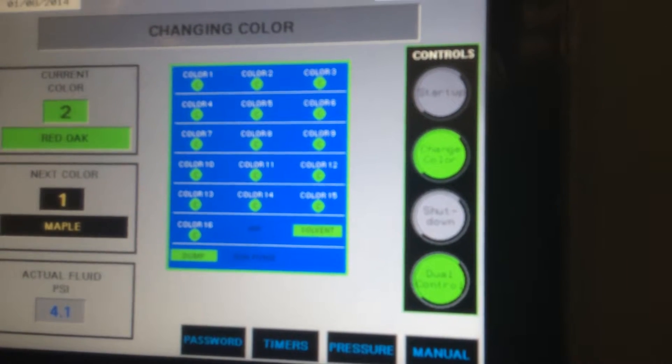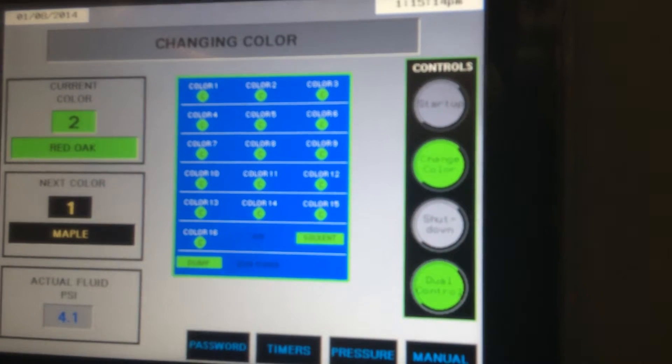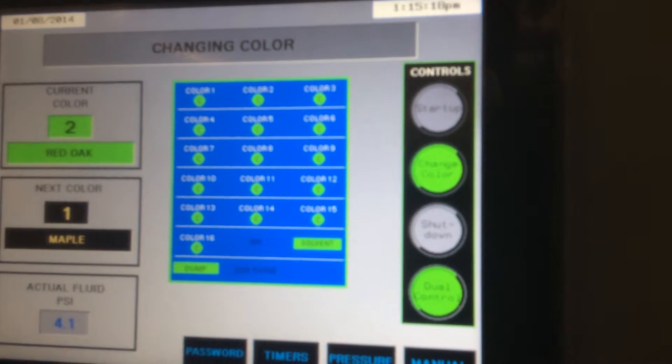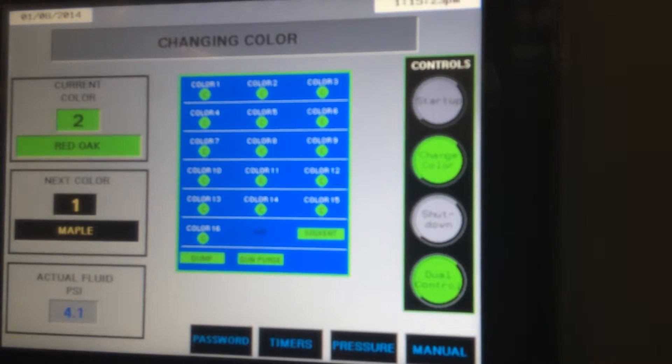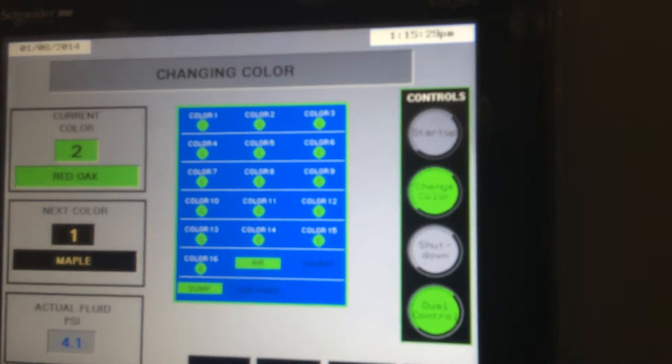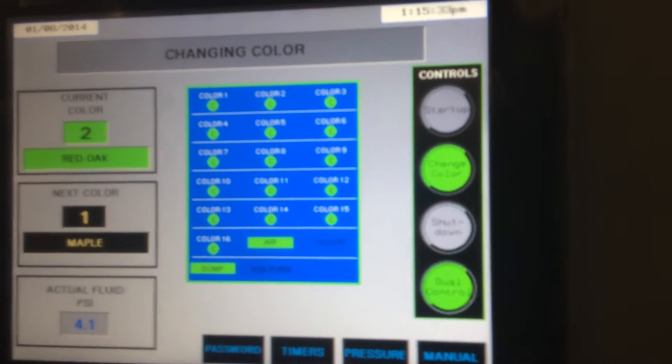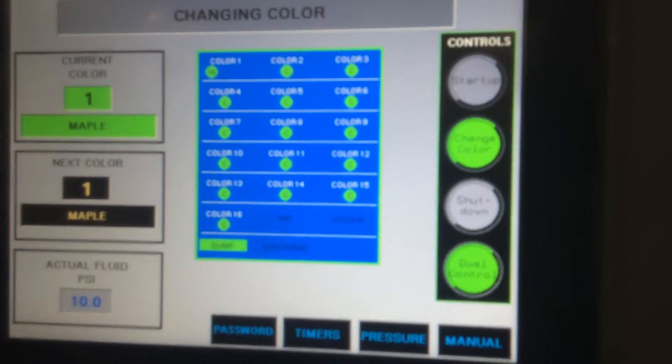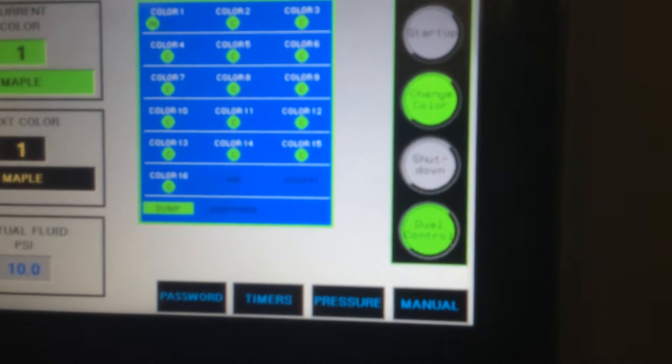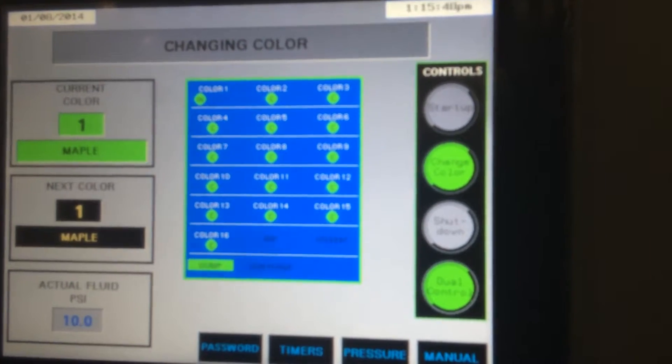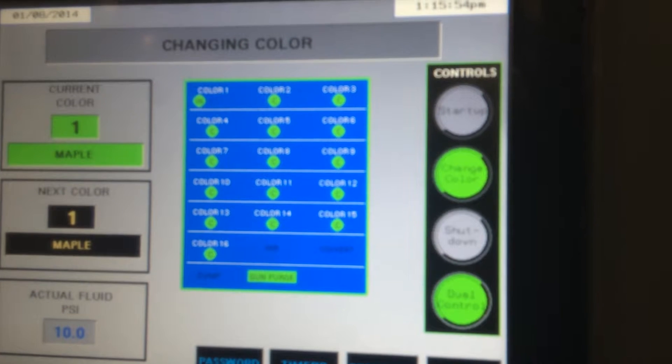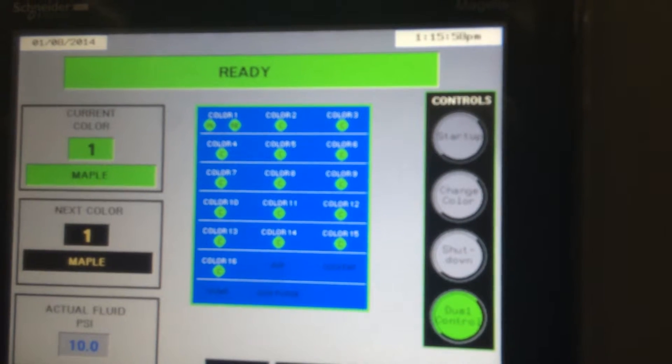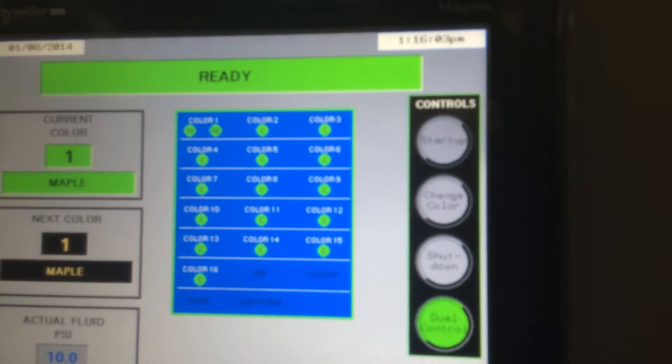You can hear the air solvent in the background. It's now triggering through the guns. It's now pushing all of the solvent out with air. The reason we put the purge to solvent is we don't want to contaminate the virgin stain. So you have good color consistency. We're now loading color one into the system, pushing air out through the dump. Gun's now trigger to load. It's now back into circulation mode that we mentioned earlier. And it's in the run ready state. You're now ready for production. You just did a color change.